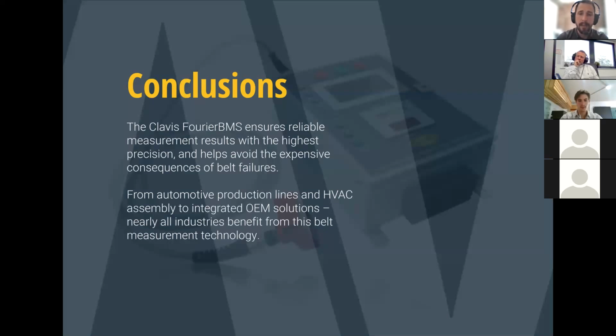Now, another product that we have is the BMS 03, which can only give an indication of what the frequency is. So we are not controlling the process, we are not readjusting the belt, but we provide assurance that the frequency is correct or incorrect, with again slight slack, tight, okay. We can have communication via RS-232 with the system. We can store the graphs as well, either the vibrations and/or the FFT, and we can provide the slack, tight, okay, and the frequency as an output.